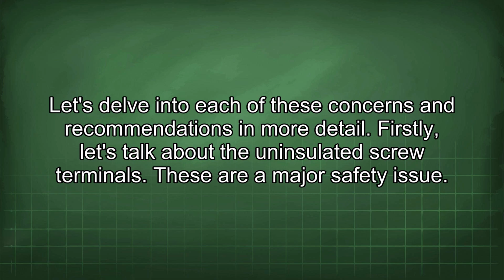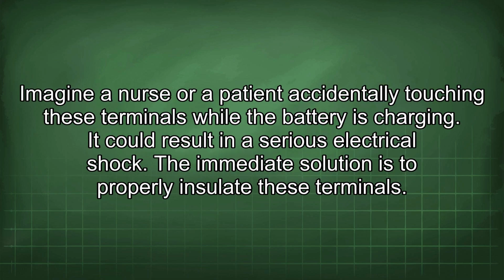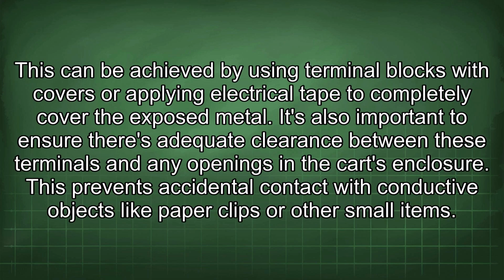Firstly, let's talk about the uninsulated screw terminals. These are a major safety issue. Imagine a nurse or a patient accidentally touching these terminals while the battery is charging. It could result in a serious electrical shock. The immediate solution is to properly insulate these terminals. This can be achieved by using terminal blocks with covers or applying electrical tape to completely cover the exposed metal. It's also important to ensure there's adequate clearance between these terminals and any openings in the cart's enclosure. This prevents accidental contact with conductive objects like paper clips or other small items.